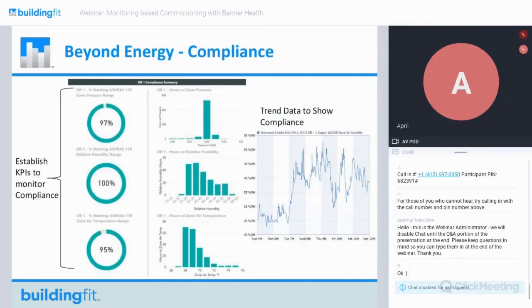The next consideration beyond energy is compliance. In the case of Banner, hospitals have all kinds of environmental compliance considerations. A really good example is in operating rooms. ORs have to maintain zone pressure, percent relative humidity, and zone air temperature within specified ranges in order to maintain an optimal environment for life safety of the patient. So those are all things that are measured and controlled by the BAS.